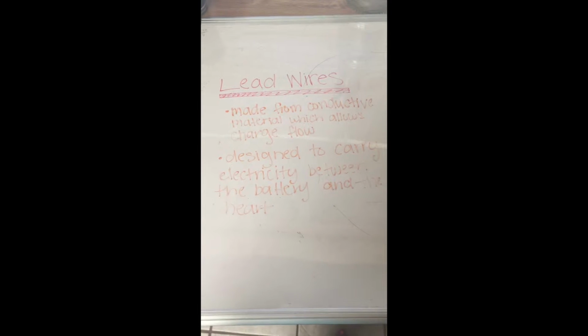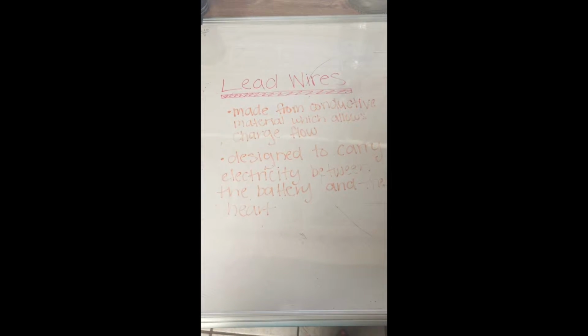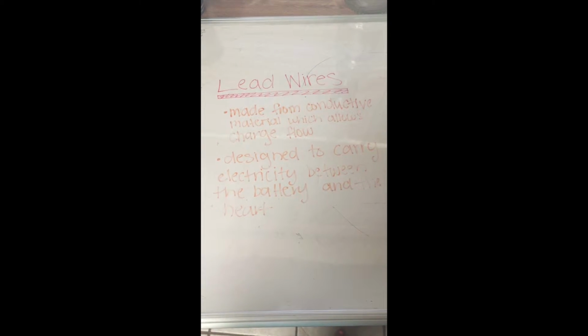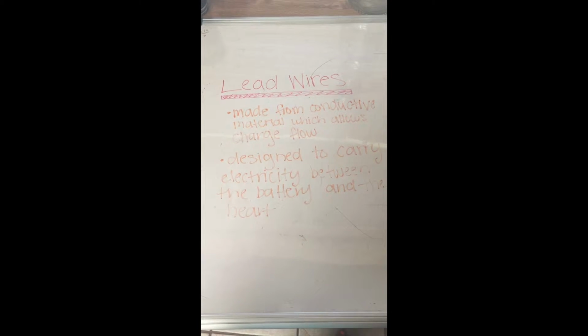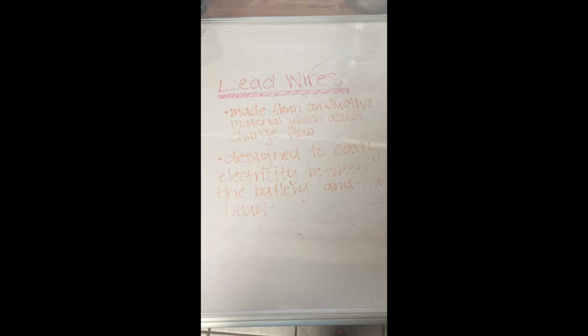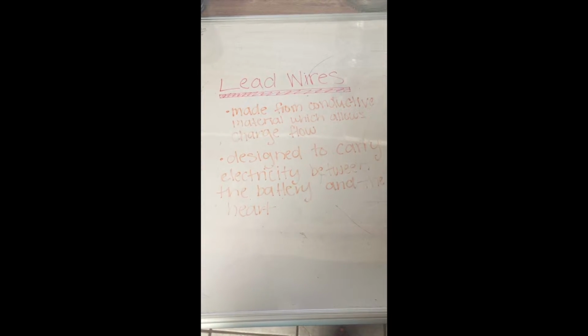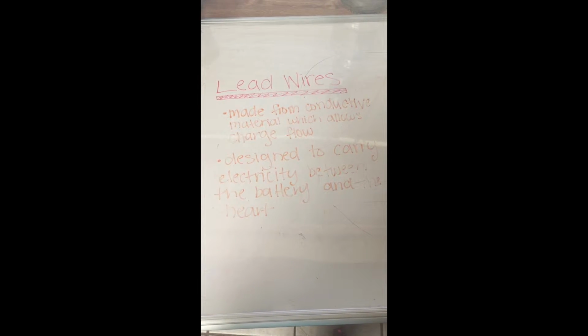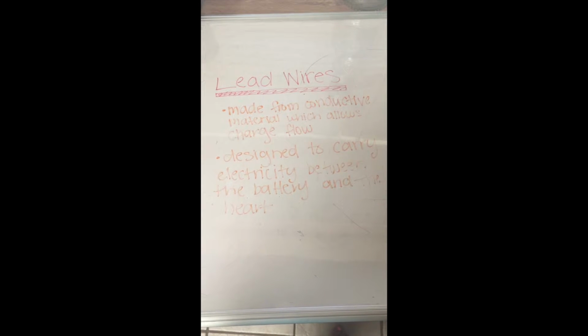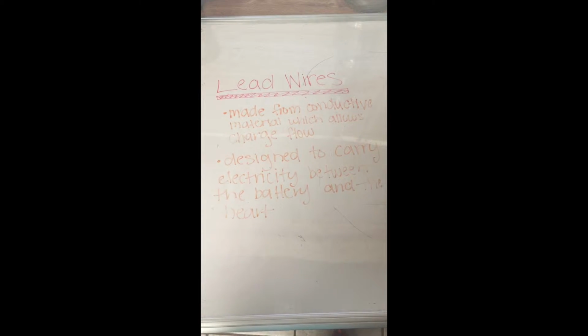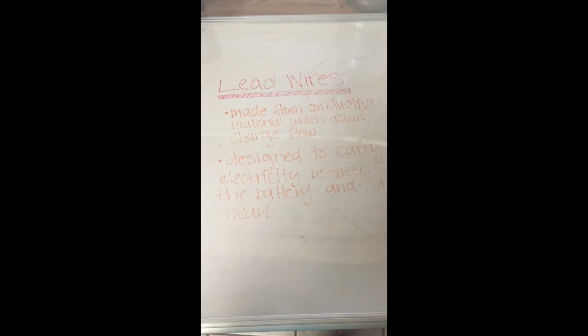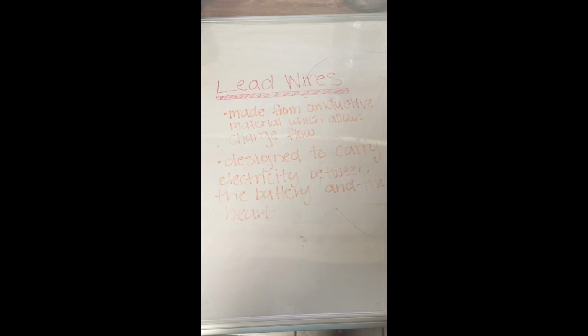The next component we will talk about are the lead wires. Since the lead wires are made up of a conductive material, they allow the charge to flow. The main property of the lead wires is designed to carry electricity between the battery and the heart. This is why the lead wires are connected from the generator and implanted into the heart through electrodes.